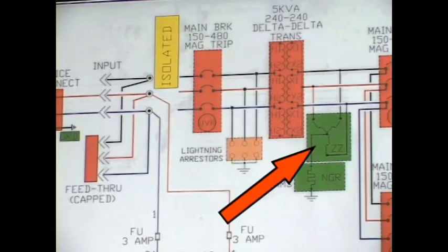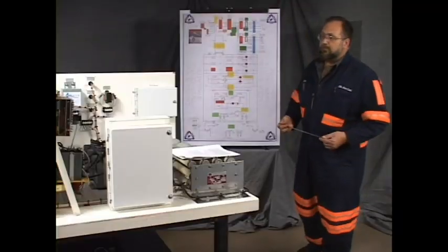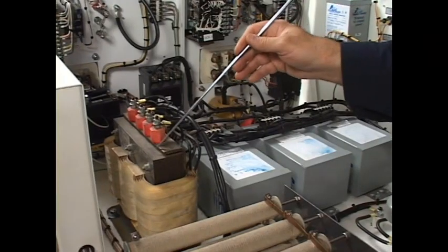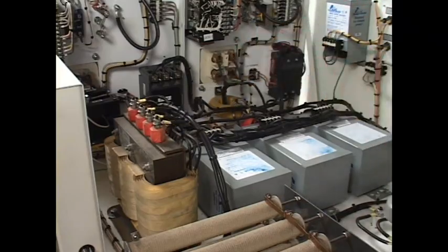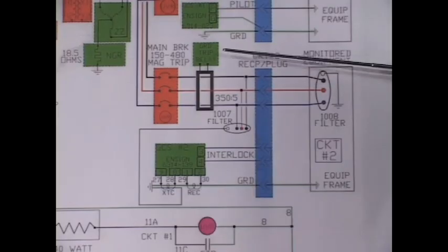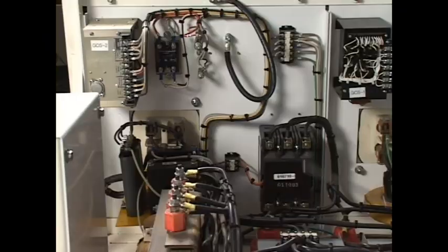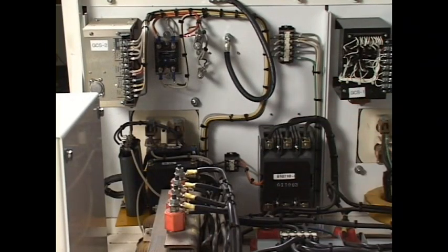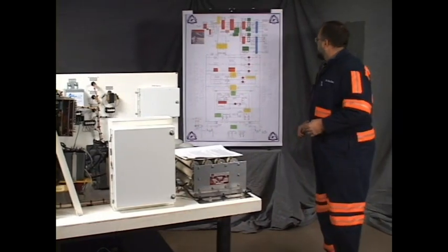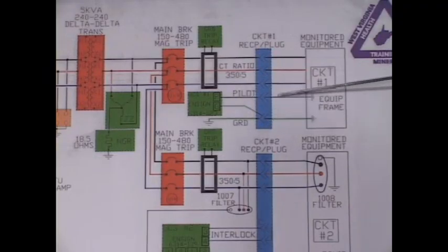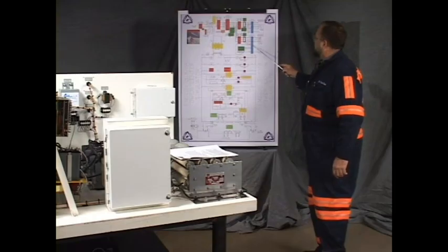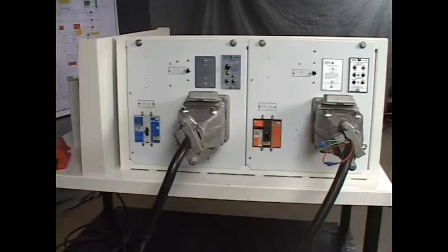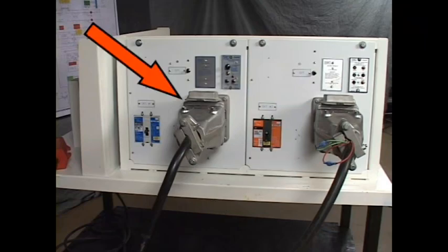You have a zigzag transformer that we use to derive a neutral for grounding purposes. It's located right here. You have a ground trip relay. It's located here. And the current transformer that feeds that ground trip relay right there. This symbol here is for the receptacle and plug for circuit 1 and circuit 2. And they're located on the front of the box. This is the plug for circuit number 2 and its corresponding receptacle. This is a plug for circuit number 1 and its corresponding receptacle.